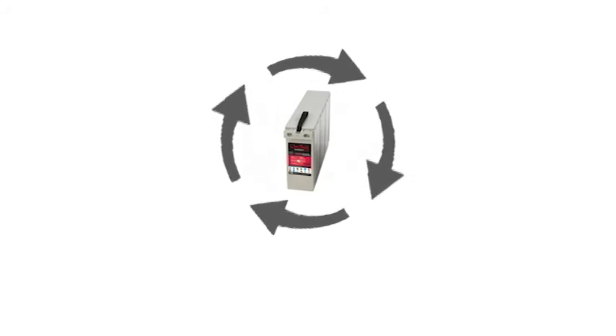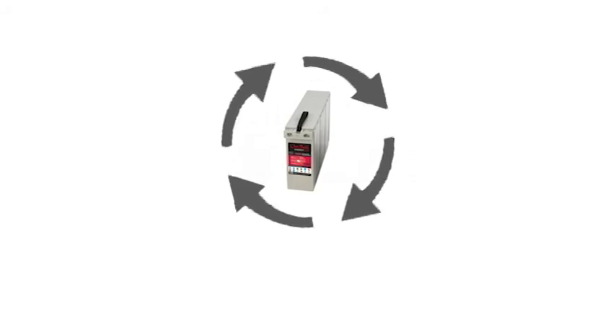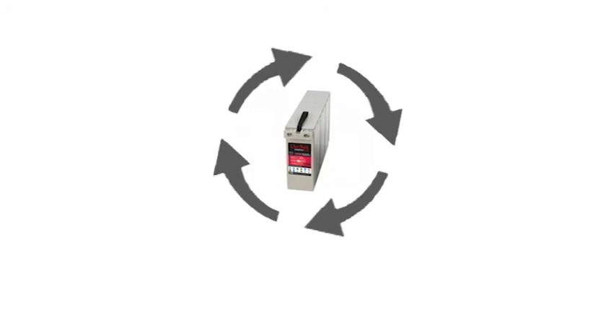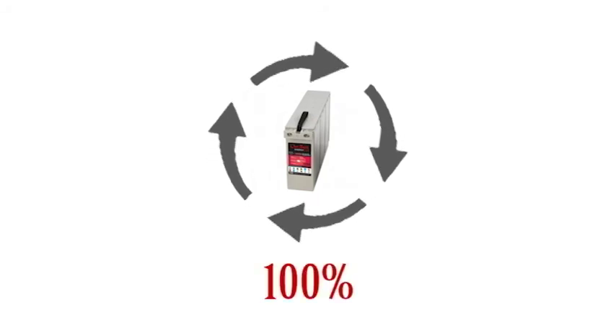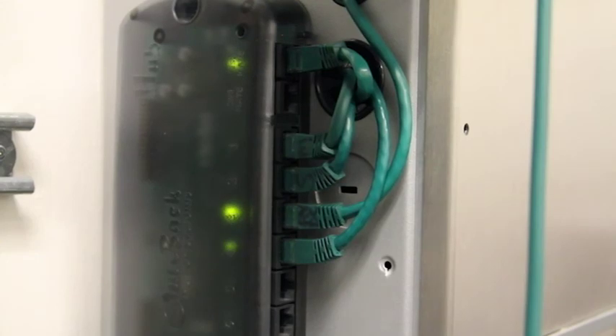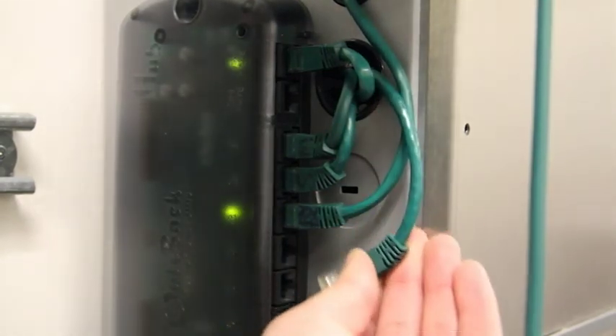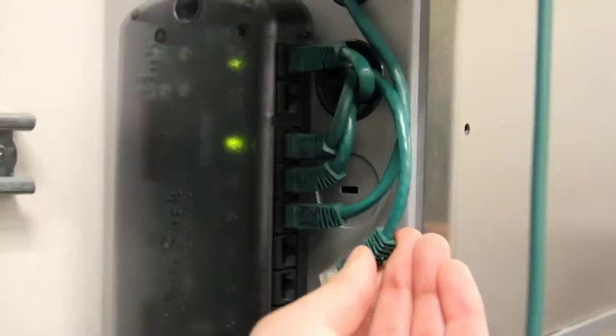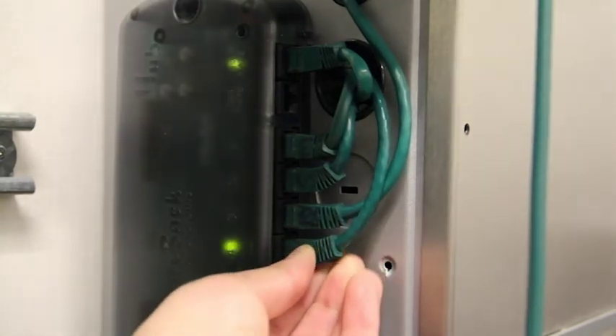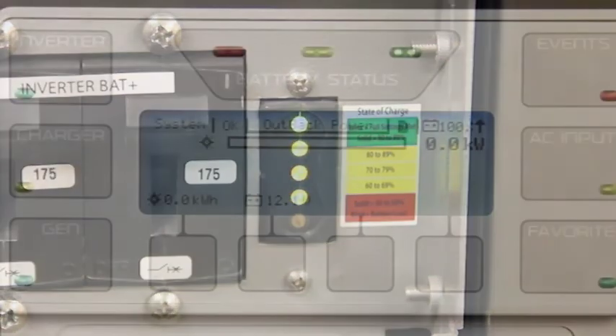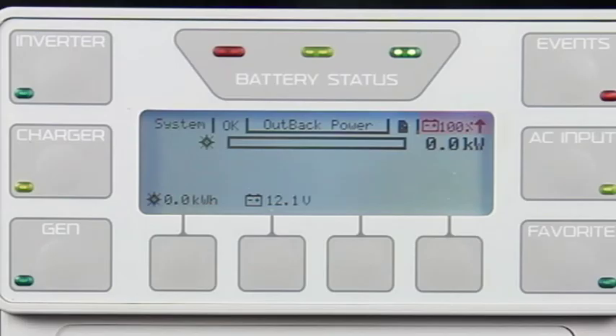Finally, you must synchronize the state of charge to your batteries. It is essential to go through a few charge cycles and have your battery bank fully charged to ensure this is done correctly. To calibrate, we simply disconnect the FNDC from the hub and replug it back in. Anytime you unplug the FNDC, it resets to 100% state of charge.